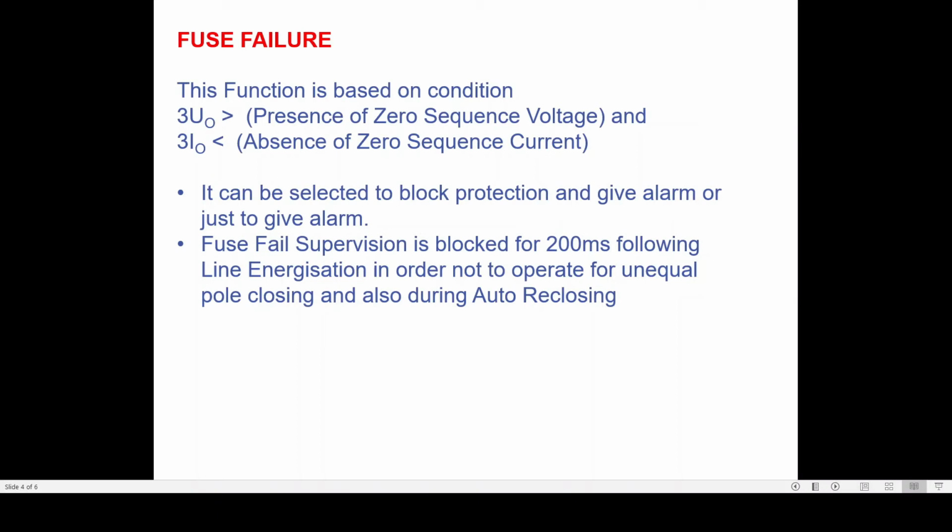Another important thing over here is that fuse failure is generally blocked for 200 milliseconds following line energization. Why it is required is that suppose you are energizing a line, then there is a fair bit of chance that the three poles of the circuit breaker, that is R phase, Y phase and B phase, generally don't close at exactly the same moment. There may be a closing time difference between the R phase, Y phase and B phase.